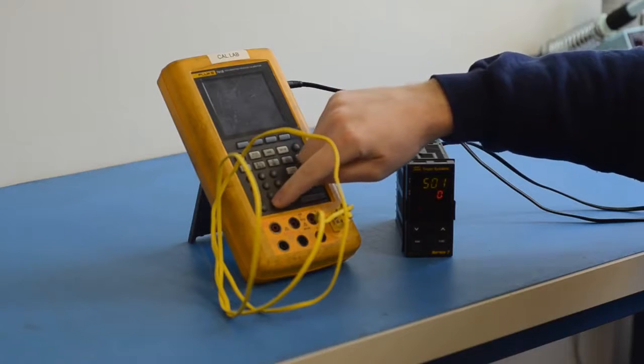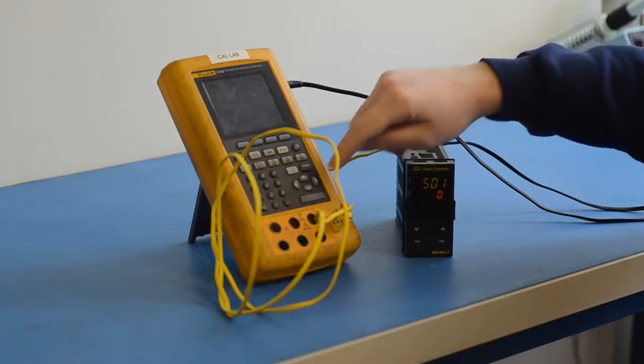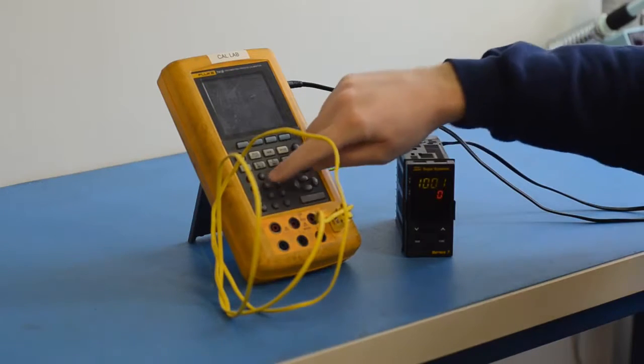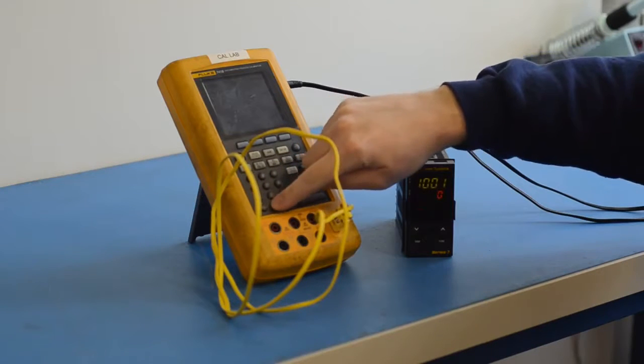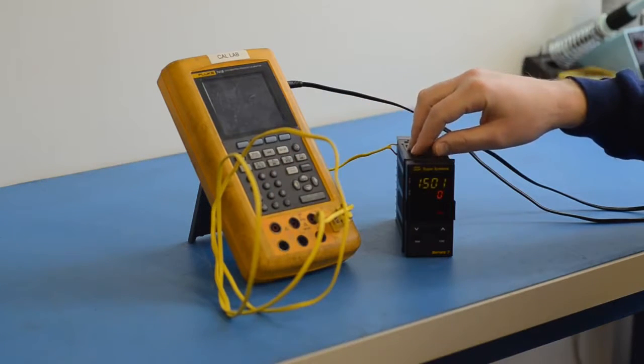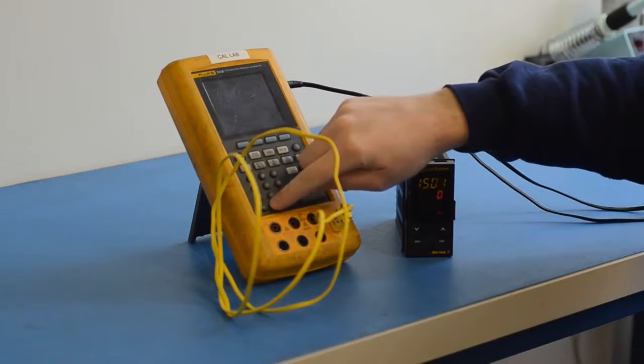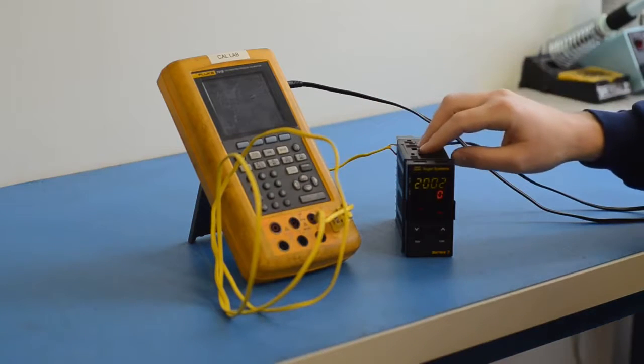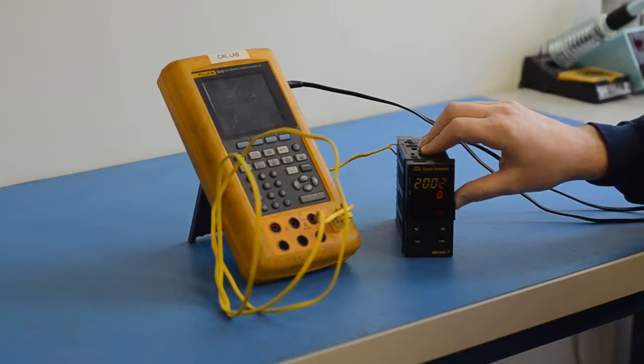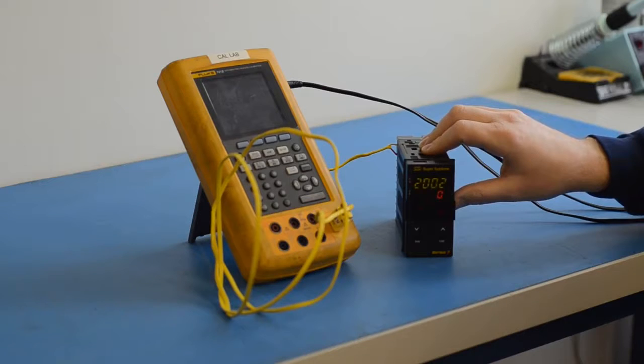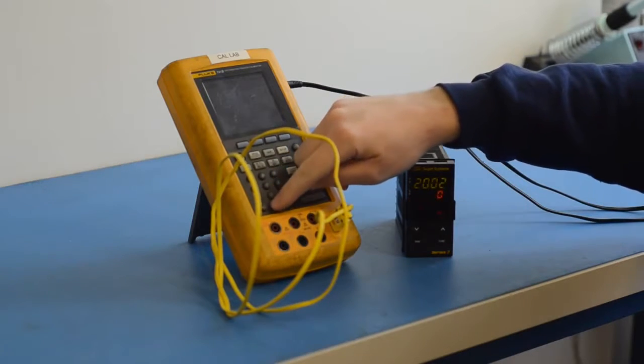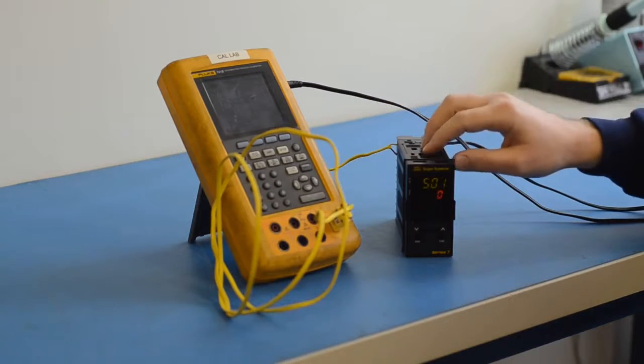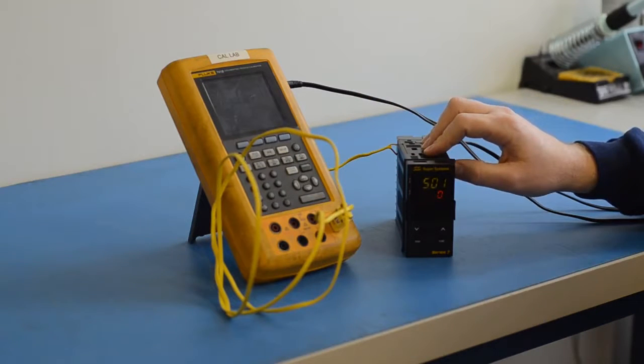I will then source in 1000 to check it over a range. Source in 1500 and source in 2000. So I am on the high range, I am 2002, so I'm 2 degrees over. On the low range, around 500, I'm 501, so I'm 1 degree over.